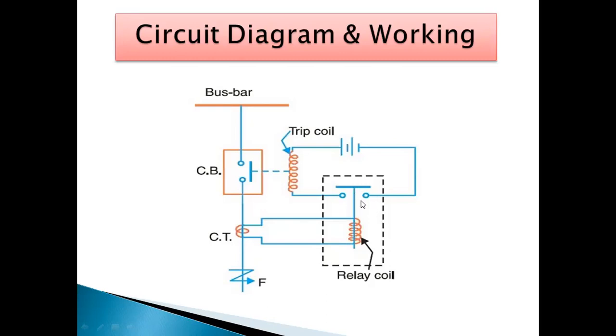These are normally open contacts. They get closed, this circuit gets completed, and supply is given to the trip coil for opening the circuit breaker contacts. Under normal condition, the circuit breaker contacts are closed. But when a fault occurs, the circuit breaker contacts open, so whatever current is flowing in this line gets disconnected. That faulty section gets disconnected from the bus bar system, so that the system remains protected.